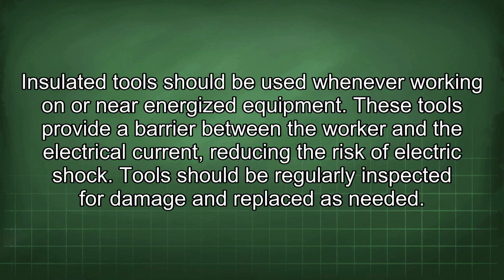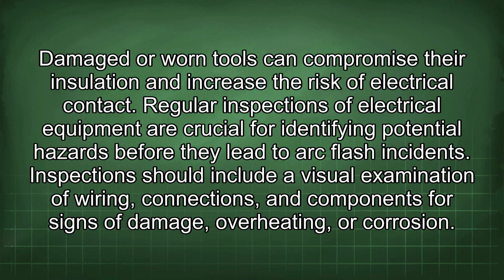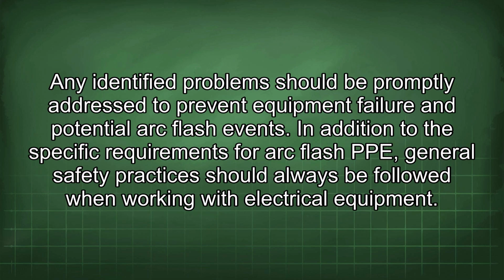Insulated tools should be used whenever working on energized equipment. These tools provide a barrier between the worker and the electrical current, reducing the risk of electric shock. Tools should be regularly inspected for damage and replaced as needed. Damaged or worn tools can compromise their insulation and increase the risk of electrical contact. Regular inspections of electrical equipment are crucial for identifying potential hazards before they lead to arc flash incidents. Inspections should include a visual examination of wiring, connections, and components for signs of damage, overheating, or corrosion. Any identified problems should be promptly addressed to prevent equipment failure and potential arc flash events.